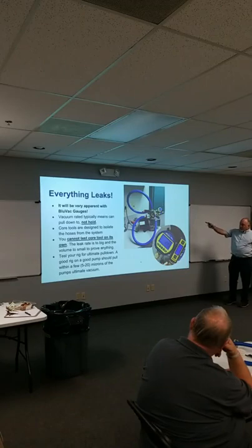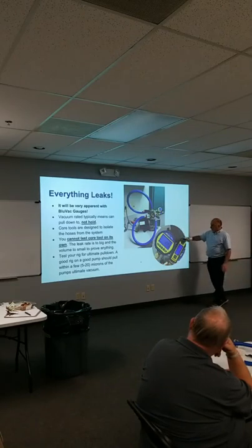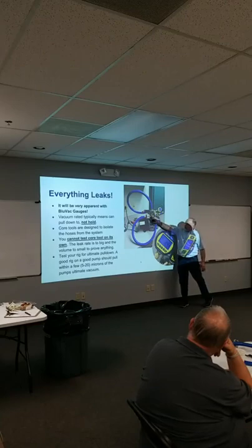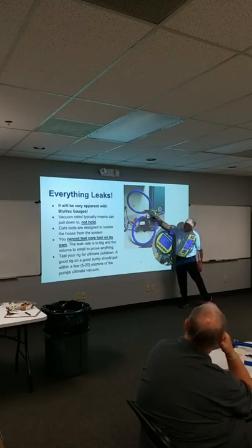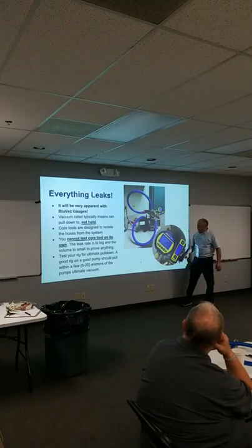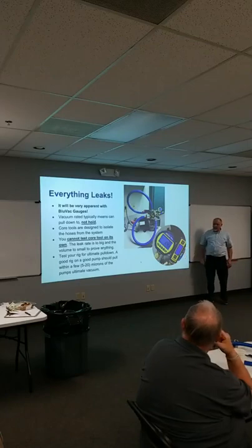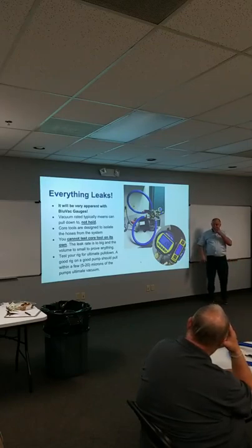Whenever you're testing a system, here I'm testing a vacuum rig, okay? You can see I've got it hooked up to the vacuum pump, one hose hooked up to the vacuum pump, and I've got a vacuum gauge here on the end of the pump. I've got a second hose connected off the top of the pump, and I've got them teed together. So at the far end of the pump, I'm reading 24 microns, and at this end, I'm reading 19 microns, okay?